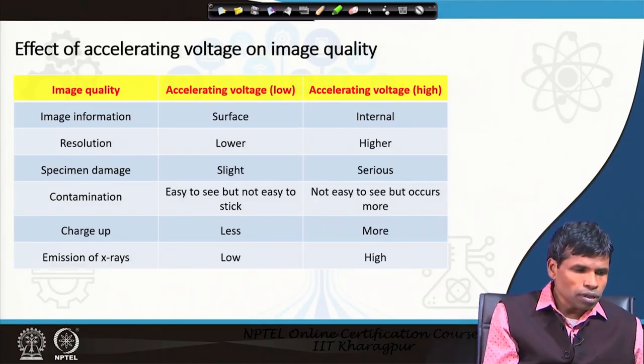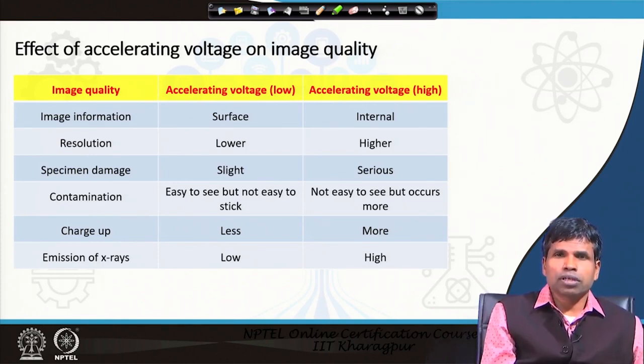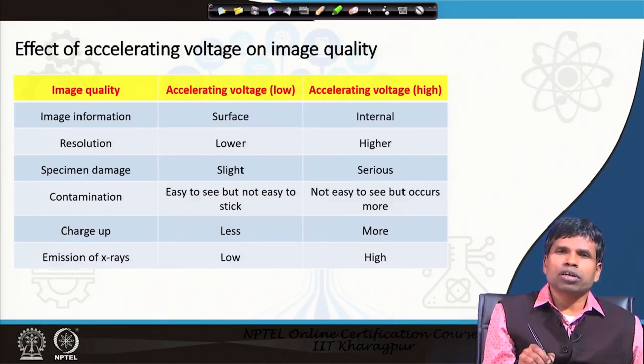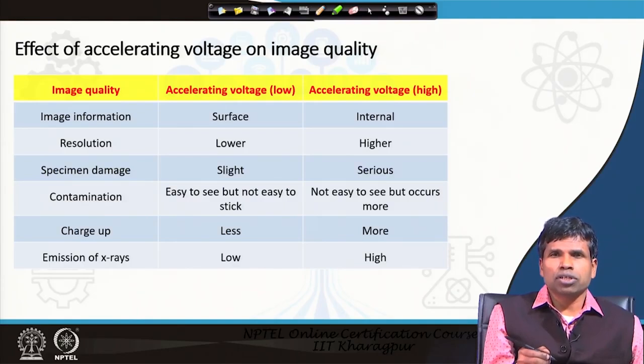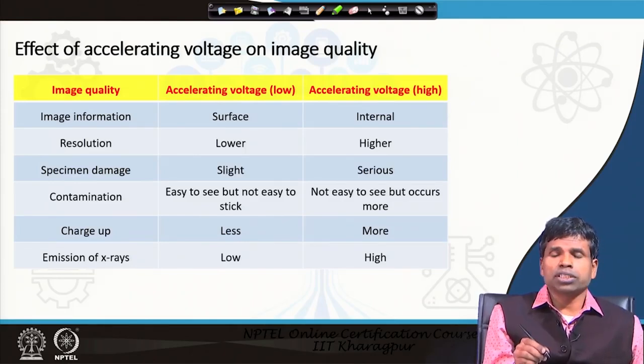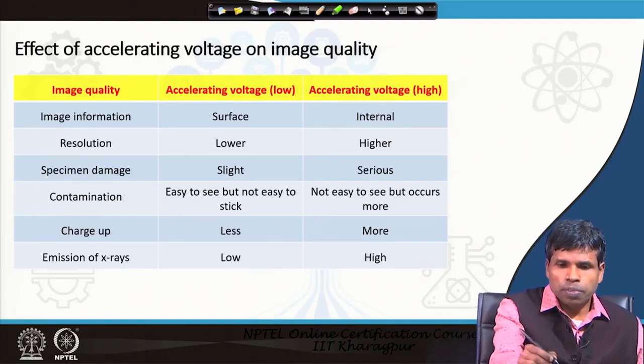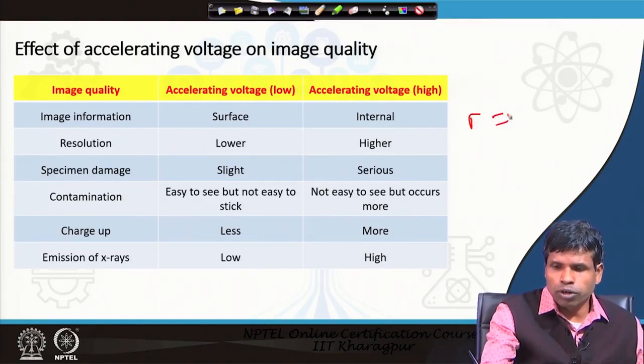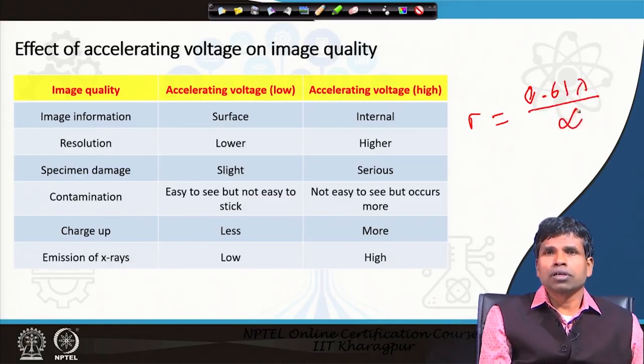First, image information: at a lower acceleration voltage we will get surface image because the electron beam will not penetrate much depth into the specimen. It strikes the surface and most secondary electrons will generate from the surface — we get information from a smaller volume near the surface. On the other hand, if acceleration voltage is high, the electron beam will penetrate deeper into the specimen, and we can get internal information. Second, resolution: when acceleration voltage is lower, resolution will be lower.